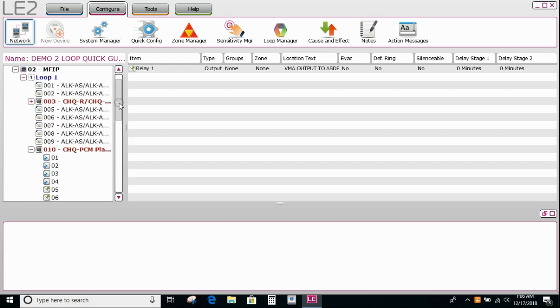So if I set all of my VMAs to tech alarm, it will come up in the panel in the other events, it will operate that relay, but it won't set the bells off. Obviously if you require that to be different, then you give the VMA input a different type of event, a fire or an evac or maybe a fault condition or something.